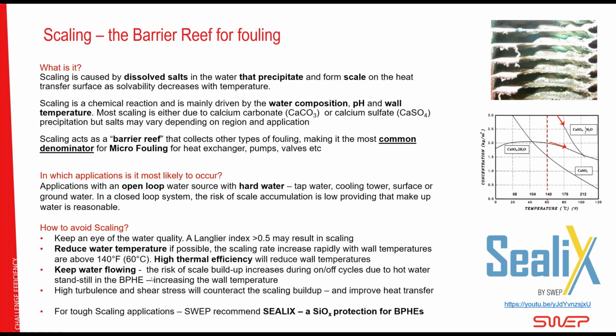Keep water flowing. What I mean by that is, if you have a hot water application and you just turn it off and turn it on, turn it off, turn it on, if that happens often, when you turn off the cooling water or the cold side, so to say, you will allow the heat exchanger to go up in temperature, maybe above the normal operating temperature. So we have seen that scaling is more prevalent in applications where there are a lot of starts and stops. So if you're able to have a soft stop and run the cold water side for longer than the warm water side, you will reduce scaling for sure. Turbulence and shear stress will also be a partner here. They will be able to clean away some of the scaling building up, as with the microfouling.